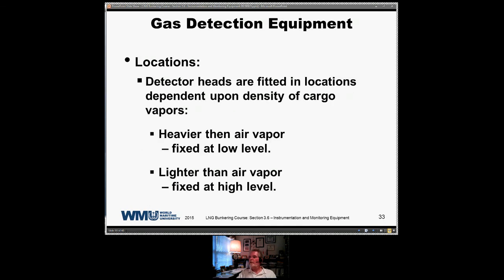Detector heads are fitted in locations dependent upon the density of cargo vapors. So if you have a cargo vapor that's heavier than air, you're going to fix your detectors at a low level. And if it's lighter than air, you're going to have your detectors at a high level. In most cases on LNG carriers, you're going to find your detectors in the overhead. Methane's lighter than air, and if it's in an ambient space, it's going to be warm enough that it's not going to be clinging.